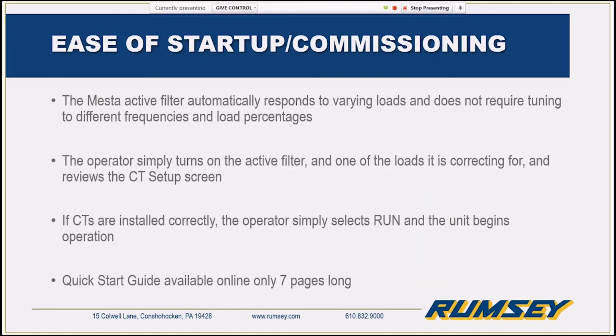And that falls right into how easy we are to start up and commission. Something that was very different from older active filters and many active filters that are out there now. First is that as long as the filter is about 15% loaded, that's enough current for the CTs to read to make sure they're going the right direction. And the unit will then respond automatically with the changes in loads.